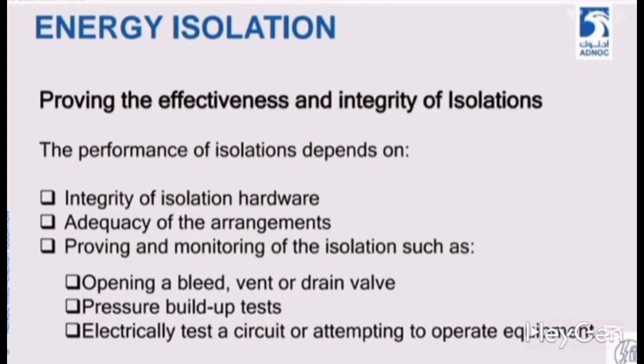Next we have the pressure build-up test. We have gauges installed from which we can check the pressure build-up behind, and the pressure ahead should be 0. If pressure is showing, it means our isolation is not ensured there, our isolation is not effective.